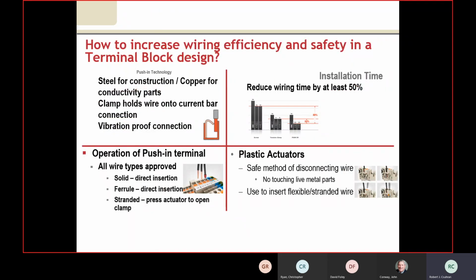One of the other things that not all customers use, because there are a lot of customers that use just screw type terminal blocks, but there are these spring clamps, and now we have a push-in terminal block. The spring clamp is great, and the push-in terminal blocks are great for applications where there's a lot of vibration, because over time the wiring gets tighter because the vibration causes the spring clamp to clamp down even a little tighter. So it eliminates the need to go in and retighten the screws before you ship it, and then retighten the screws again when you're in the commissioning process.